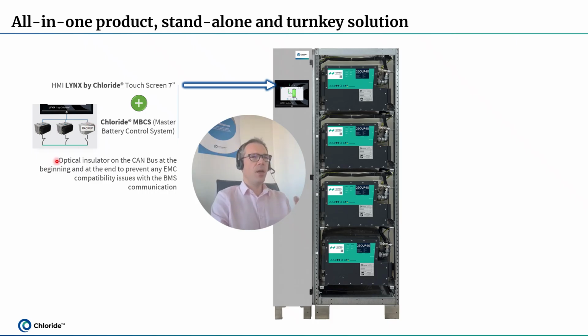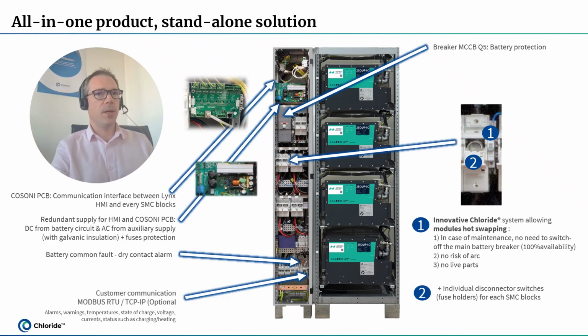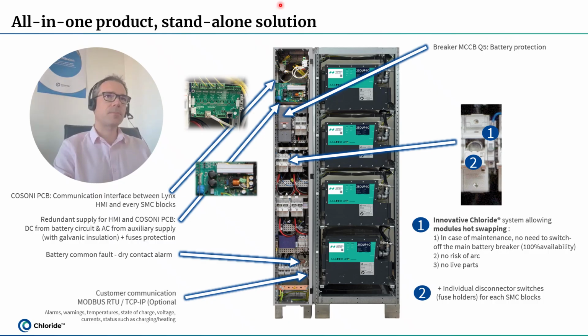We have also integrated an optical insulator on the CAN bus, the communication bus between the touchscreen and the Chloride battery monitoring system. So we have integrated this optical insulator at the beginning and at the end of the communication link to prevent any electromagnetic compatibility issues with the battery monitoring system. So it's a kind of return on experience that we get when we started 5 years back. So to make the communication link stronger, we have integrated this unique protection. Next point.